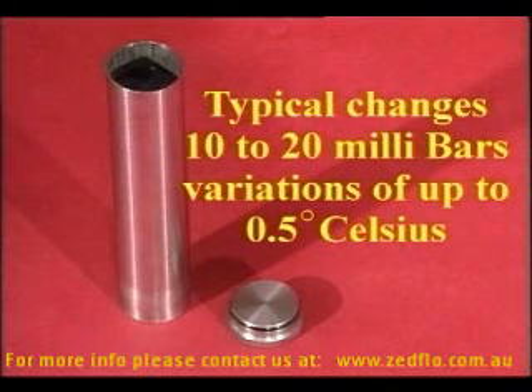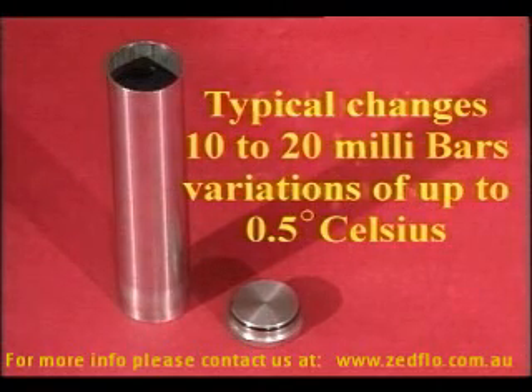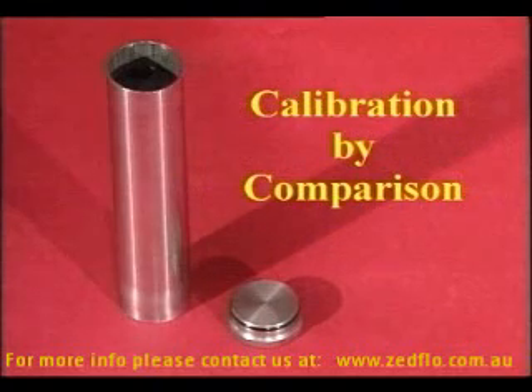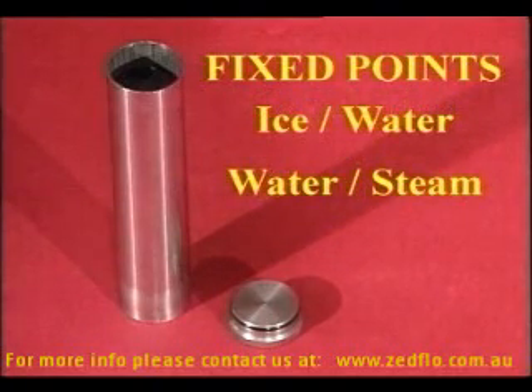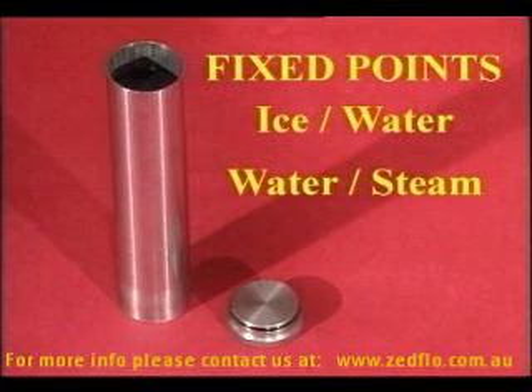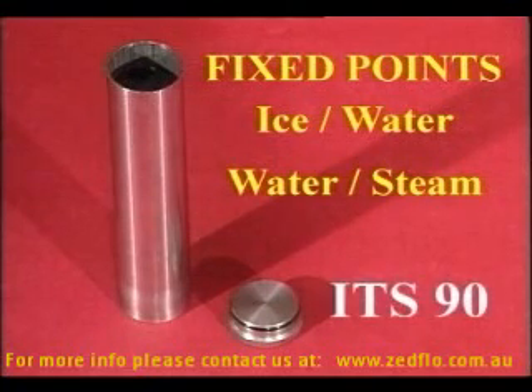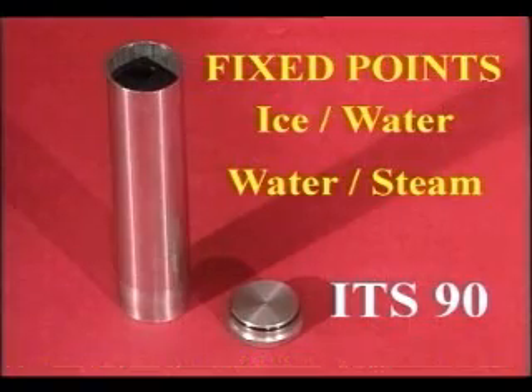The methods we use for calibration in this stirred liquid bath are very similar to those used in the metal block bath. We calibrate by comparison, except where we use ice and water or water and steam, in which case they are called fixed points. The fixed points, the steam point and the iced water point, are called secondary points on the temperature scale of 1990. But that's not all the Isocal 6 will do.